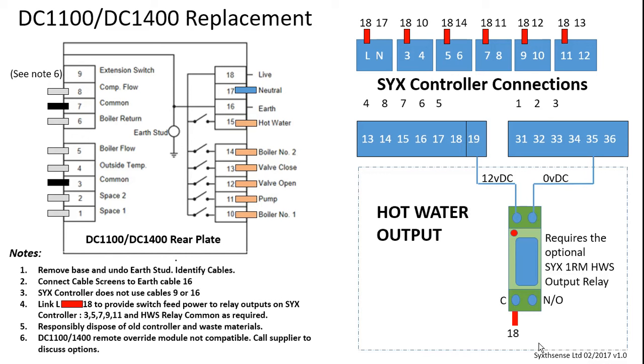If you have the requirement of providing a hot water time channel from your existing DC1100 or DC1400 controller, you will need to obtain the SYX HWS option relay at the time of purchasing your SYX controller. This is an optional extra. Please be aware that this does not come with the standard SYX controller, so you need it if your controller needs to switch the hot water channel. Because the hot water output also needs a switch feed, you're going to need to wire the live connection also as a switch feed into the option relay shown at the bottom of this image, terminal 18, into the common.